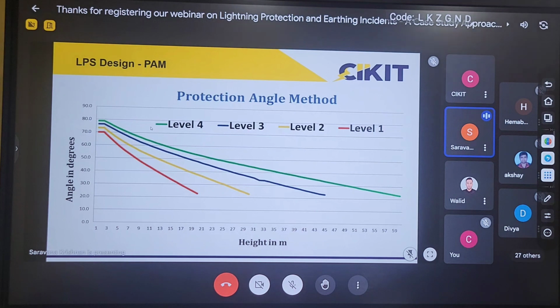From this graph, I have to take the value of the angles. If it is 2 meter, I have to extend a line from 2 meter and see what the particular angle will be for this site condition. If it is 2 meter and I go for level 1 protection, the angle will be 70 degrees. If I extend the line up to level 4, the value will be around 78 degrees. So, from this graph, I have to take the value of the angles.